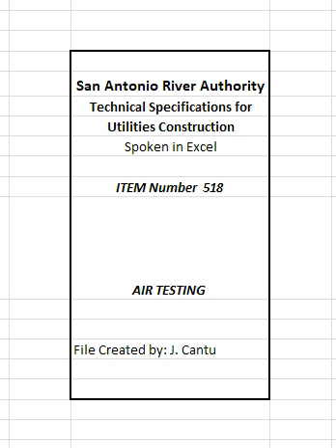Different sections of pipe are to be tested separately. For sections of pipe less than 36-inch average diameter, the maximum time allowable for the pressure to drop from 3.5 pounds per square inch gauge (psig) to 2.5 psig shall be computed by the following equation. T equals 0.085 times D times K over Q. T equals time for the pressure to drop 1.0 psig in seconds. K equals 0.000419 D L, but not less than 1.0.